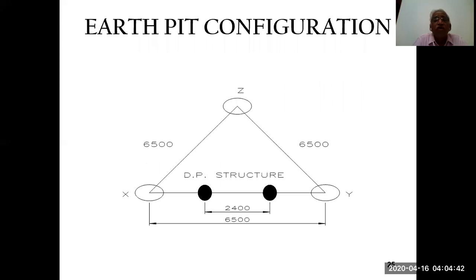Now the earth configuration is shown here as X, Y, Z, and you can see clearly that the distance between them is 6500 millimeters or 6.5 meters. Two are marked as the DP structure, and the other two are marked in dark with a 2400 millimeter gap. As mentioned, two connections have to be taken independently from the neutral, brought down and connected, one at X and one at Y, and Z can be used for the body.